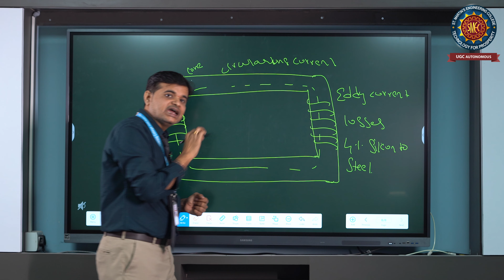Then the core can be built using the lamination technique. Simply, consider a white paper as a silicon steel sheet. This sheet is cut into smaller pieces, and the size depends on the requirement, 0.3 to 0.5 mm. These are bunched together to form your core. This is called lamination. By using this technique, we can again reduce the conductivity of steel and reduce the eddy current losses.